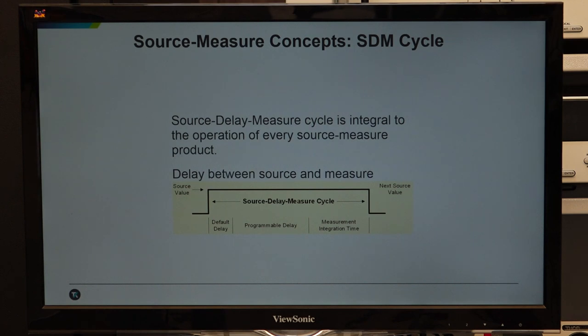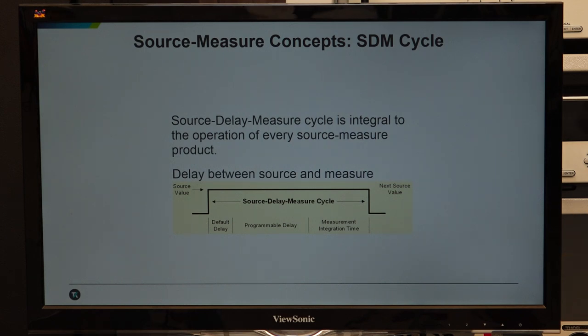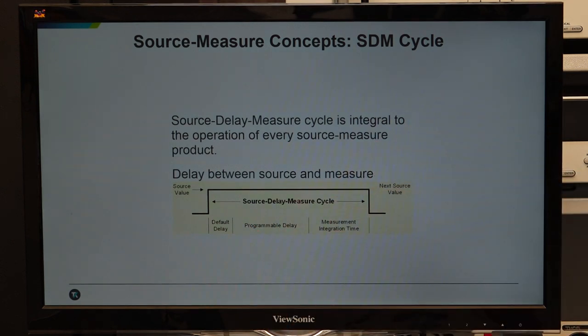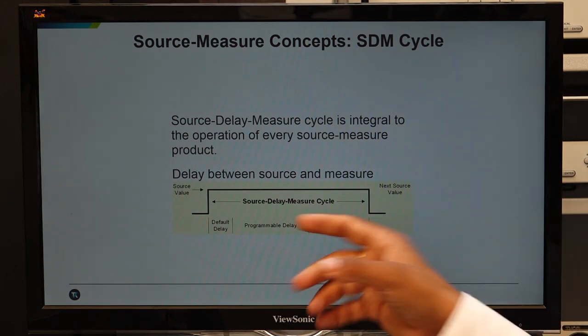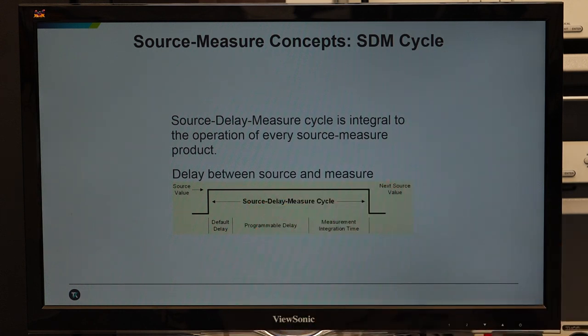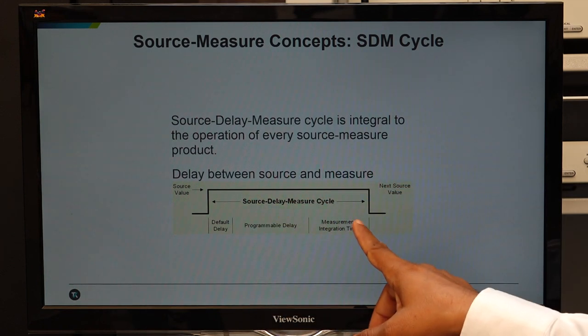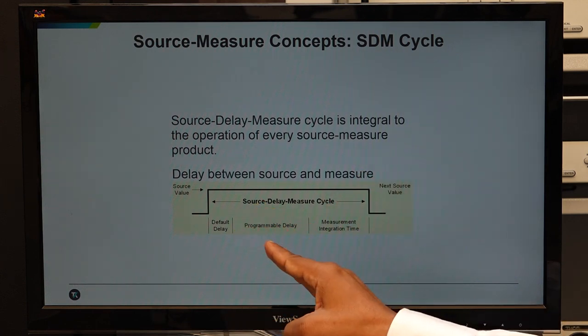Another important aspect of SMU operation: SMU can be configured in various ways like power supply, current source, DC electronic load, and measurement. For any single point measurement, the SMU first stabilizes the source. After any user-defined or auto delay, the measurement happens. Measurement occurs after source stabilization and delay. In material applications where faster measurement is needed, this cycle can sometimes create problems, in which case a stand-alone dedicated meter can be used.